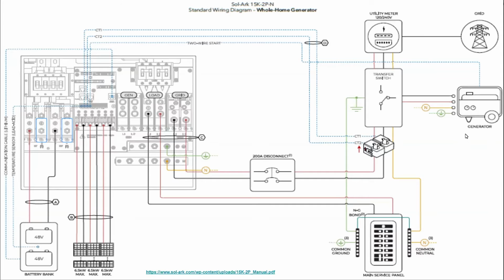Sorry to cut you off, but a question has come in. It says, is it correct that under the Sol-Ark design, when the system acts as a microgrid, the controller sets the system frequency and the generator follows the system frequency? And under this design, you could have a 6 kilowatt generator with 20 kilowatt hours of batteries.